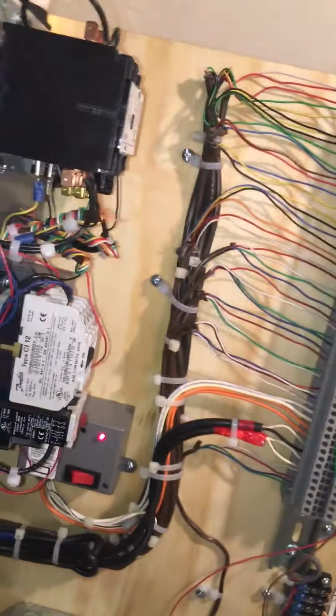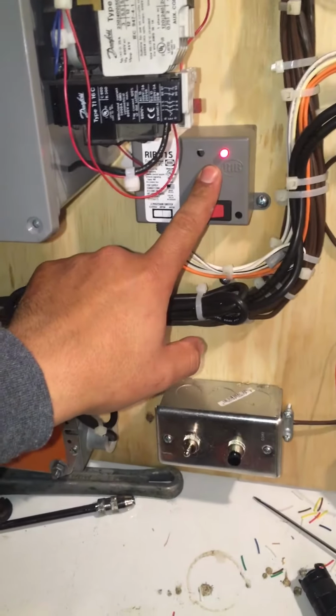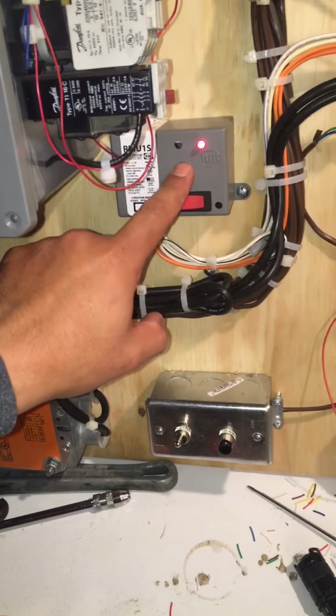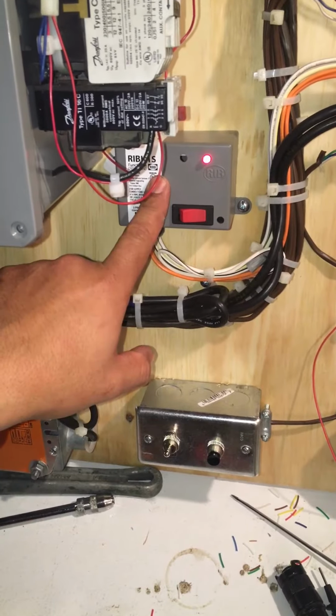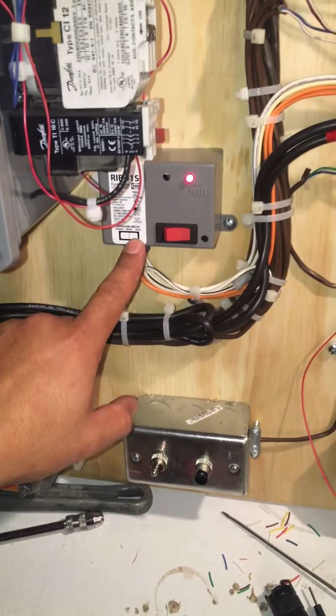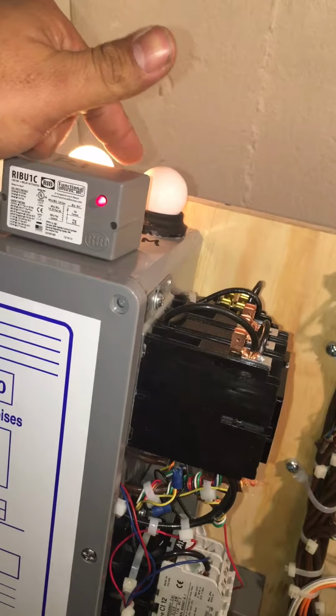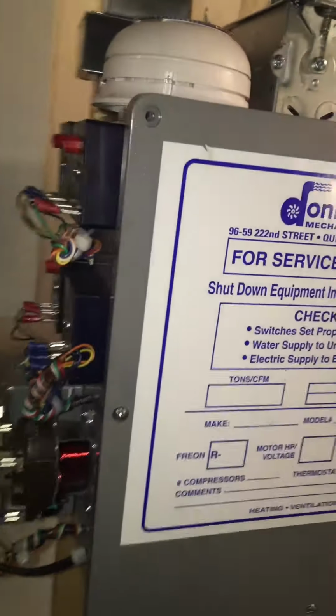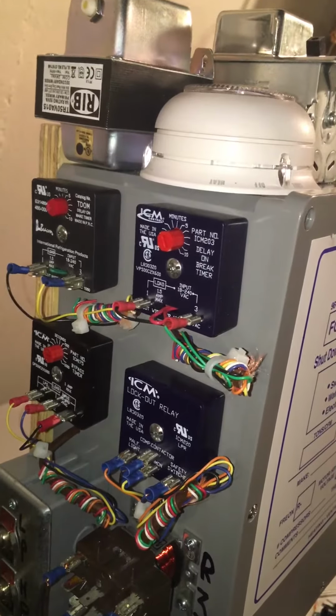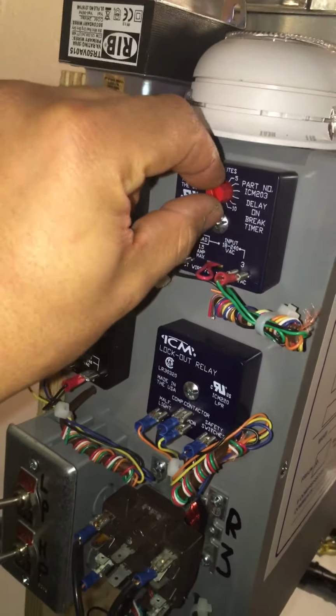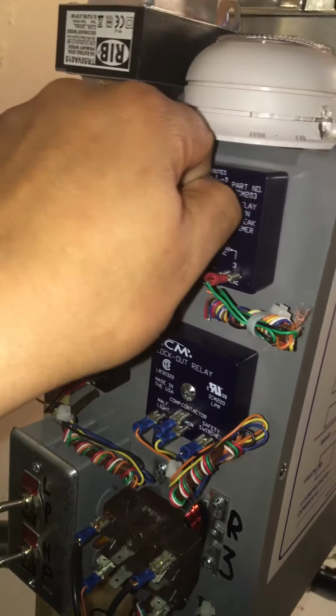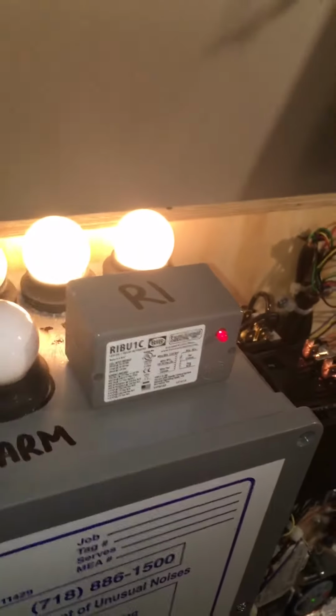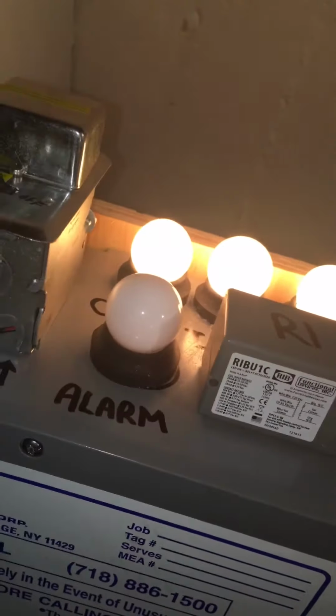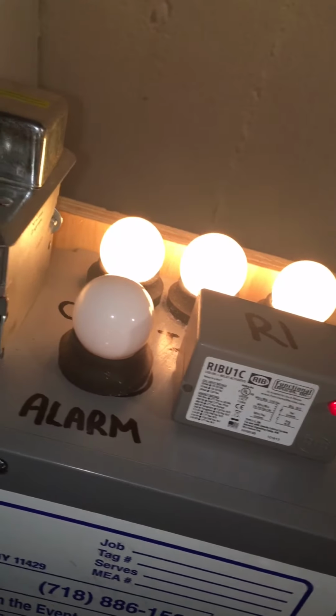Now you may notice that the call for cooling has engaged the HOA switch for the condenser water pump. That light is not engaged yet due to our delay on break timer over here to prevent the short cycling of the pump turning on and off, and also the compressor. So if I crank this down, there goes that, and then we just engaged our compressor again.